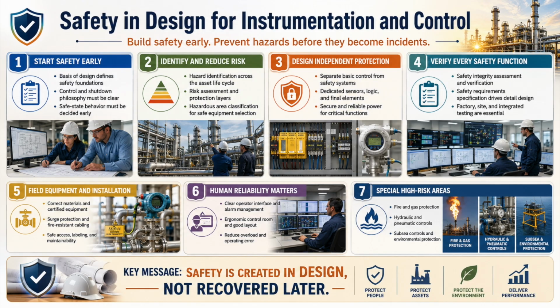Every instrument and actuated valve must therefore be assessed for loss of electrical power, loss of instrument air, loss of hydraulic pressure, internal failure, communications failure, and restoration of energy. The design must answer one direct question. When this device fails, what does the process do next?